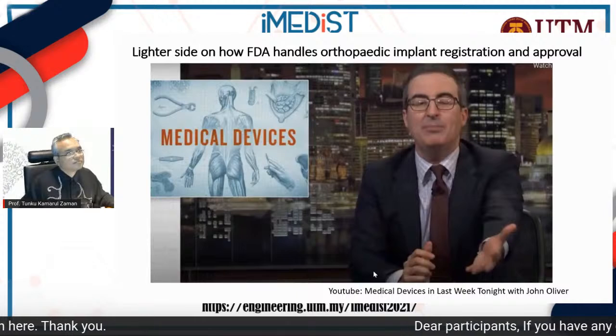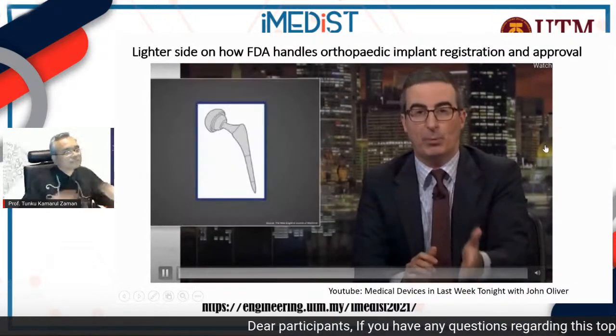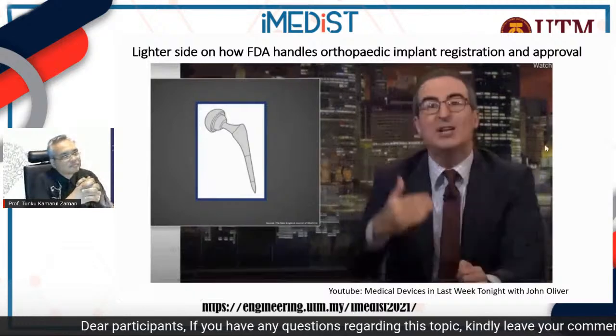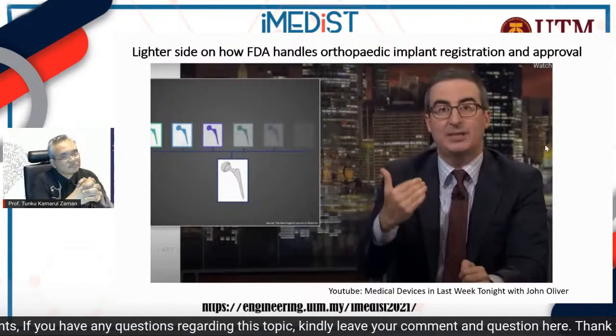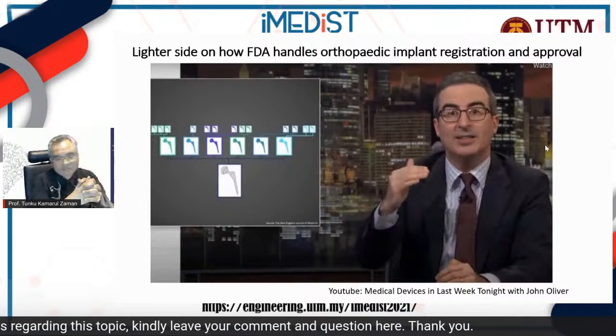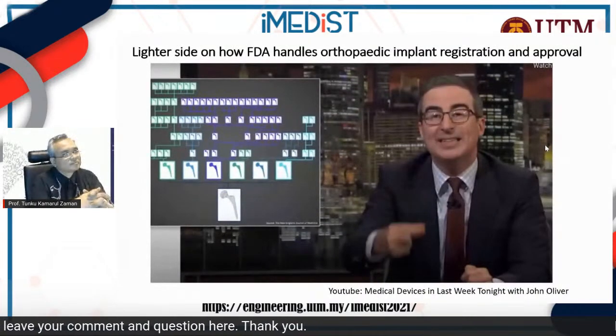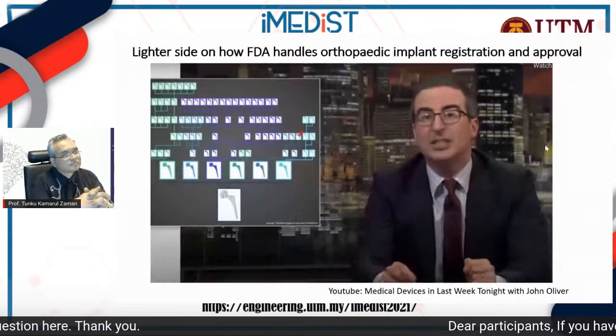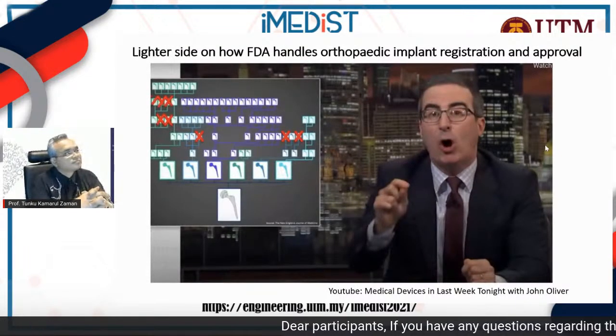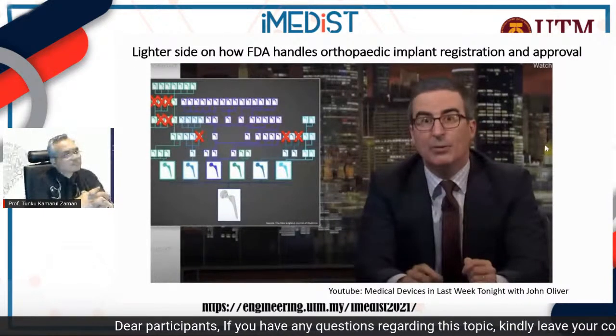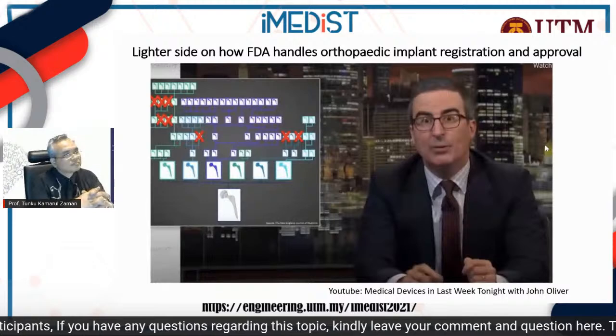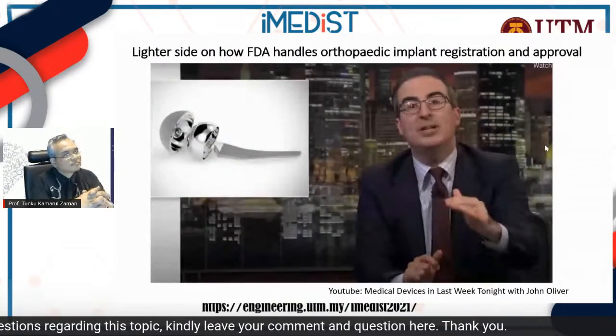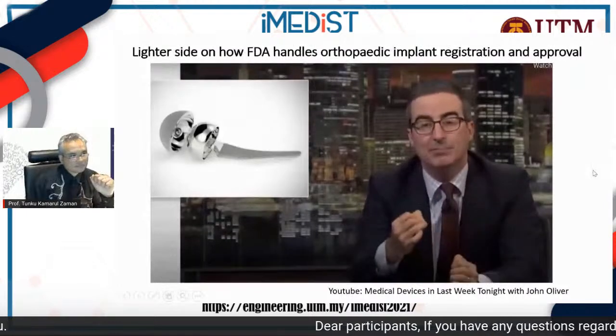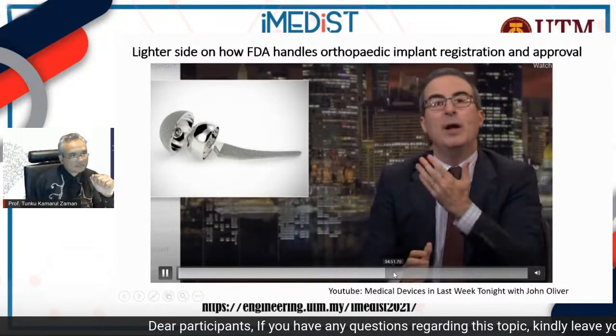Let me show you. In 2008, a company called DePuy received FDA clearance for a hip replacement based on its substantial equivalence to 6 previous devices, all of which were cleared because of their similarity to devices before that, and before that, all the way back to hips that were on the market in 1975. Now, incredibly, some of those devices have since been taken off the market by their manufacturers because of their high failure rates, but under FDA rules, DePuy could still use them as a basis for getting their hips cleared. And the thing is, DePuy's hip really would have benefited from clinical testing in human beings because there was a big problem. While it may have looked similar to its predecessors, it was crucially different in that both its ball and socket were made out of metal. And it turns out that when metal rubs against metal, bad things can happen.